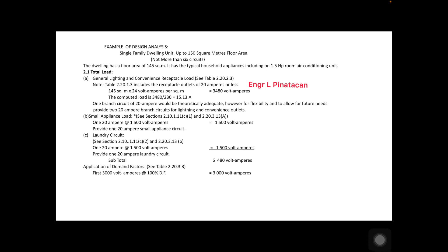Next, we need a laundry circuit for the laundry machine, referenced in section 2.10.1.11(c)(2) and section 2.20.3.13(b). We allocate 20 amperes at 1,500 volt-amperes apparent power for the laundry machine, providing a 20-ampere laundry circuit. This gives us a total of 6,480 volt-amperes.